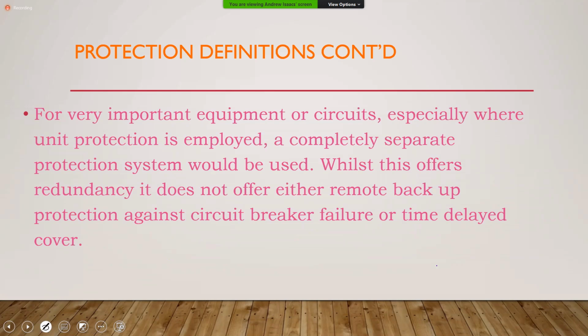They are going to the same breaker, remember the switchgear we're dealing with now, so you go into the breaker on different contacts. This helps to keep the two systems separate, so that what may cause the first system to fail would not be replicated in the backup, because then you'll just be back at square one.